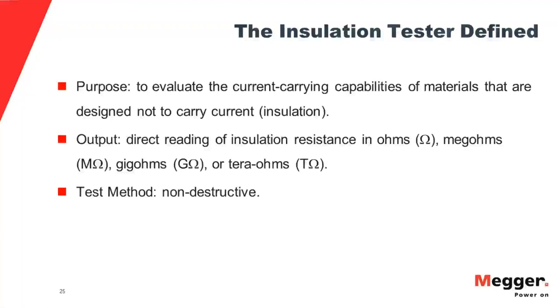And the bottom point there, the test method is non-destructive. In order to measure insulation, you need a lot of voltage, but you do not need very much power because there is very little current involved in an insulation test. If there's much current passing, that's telling you that it's not insulation anymore. So you don't need very much current to do a good insulation test. Consequently, the testers have a lot of voltage but very little power, and they are non-destructive and non-injurious at the same time. They can sting you a little bit, but even a 15 kV tester can't actually injure the operator himself. But at the same time, the test item can be dangerous, and we'll come back and talk about that.